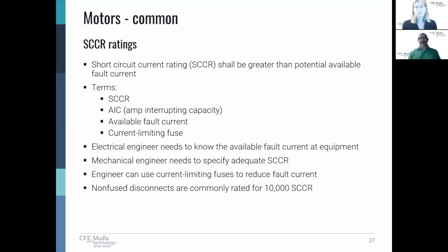So we're going to use SCCR and coordinate that. And mechanical and electrical engineers need to talk. Mechanical needs to ask, hey, what's the available fault current? What should I rate these disconnects at? And know that most standard non-fused disconnects are around 10,000. So if your engineer says, I got 25 or 35,000 amps, then you're going to have to move very likely to a fused disconnect. And you need to specify that and understand that early on. So not only do you comply, but you also don't put anyone in danger.